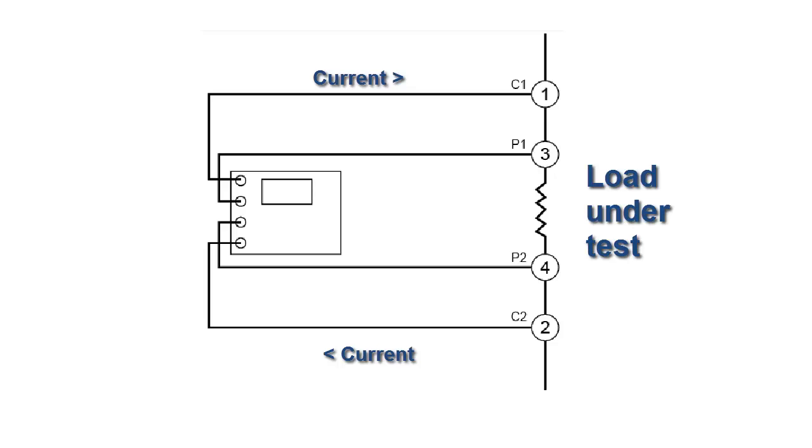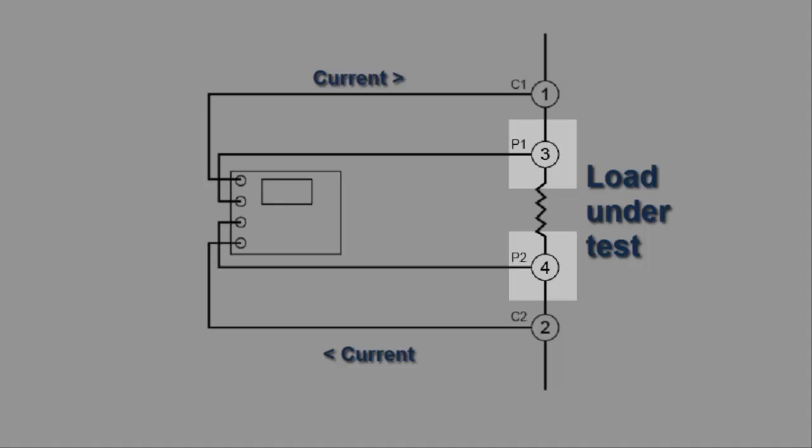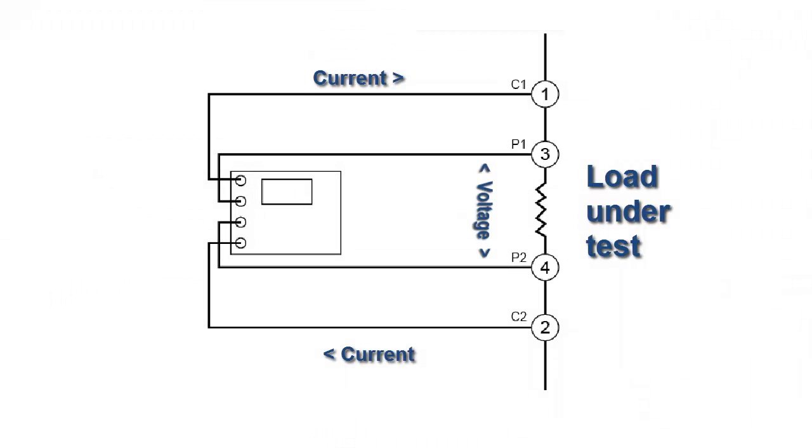In addition, the Kelvin technique employs a second pair of probes, labeled 3 and 4 on the screen, to sense voltage. The second pair is often called the sense probes. The placement of these probes ensures that only the voltage across the load is measured, independent of any resistance contributed by the current or source probes.